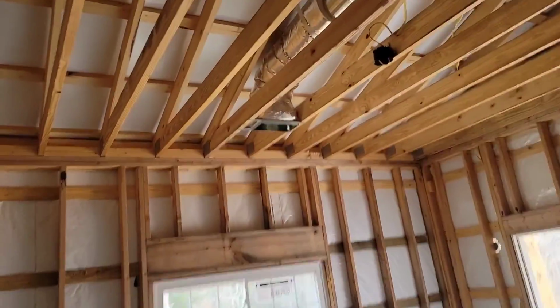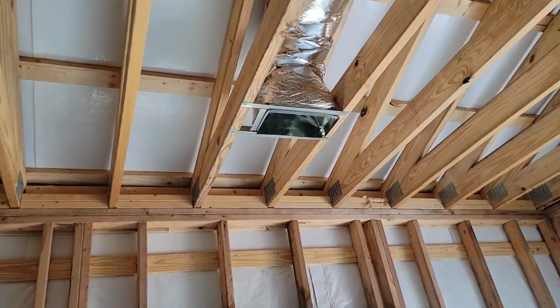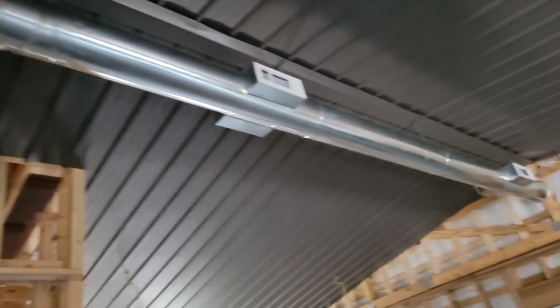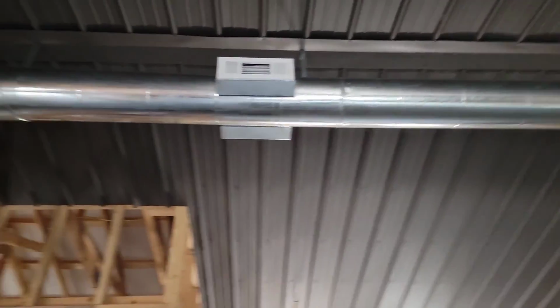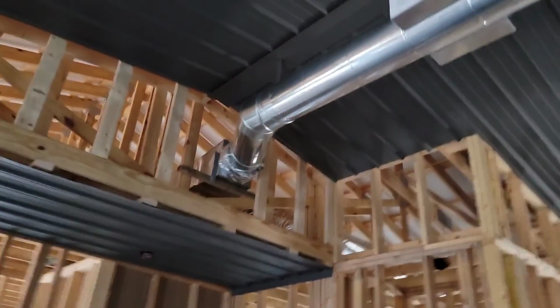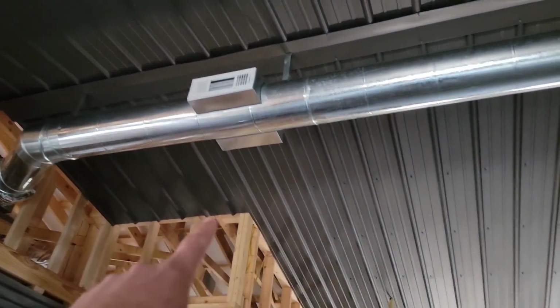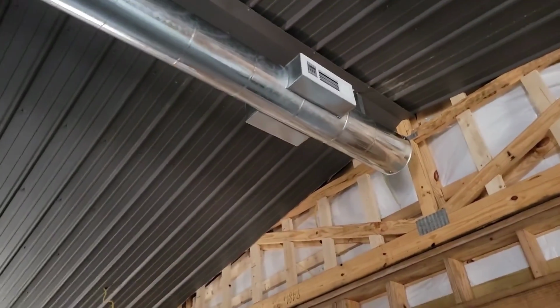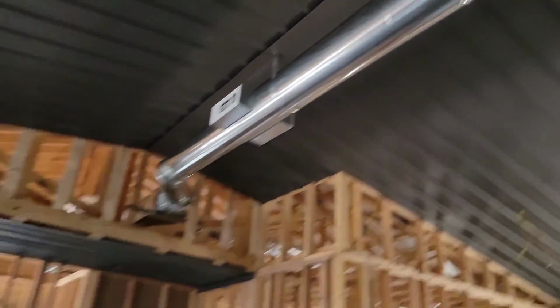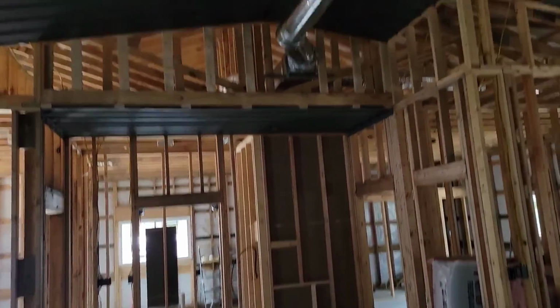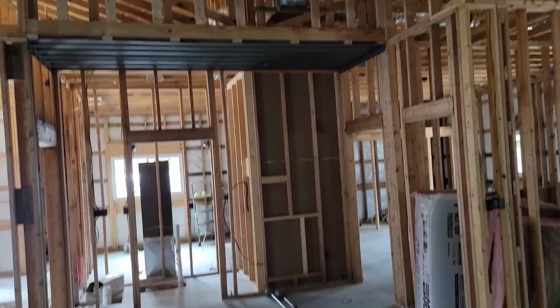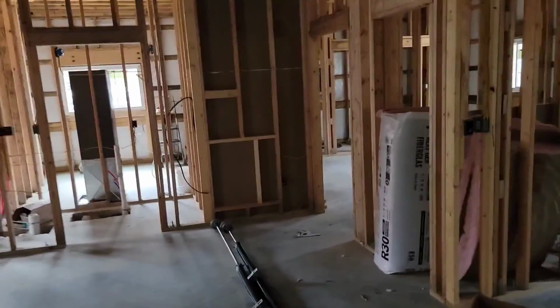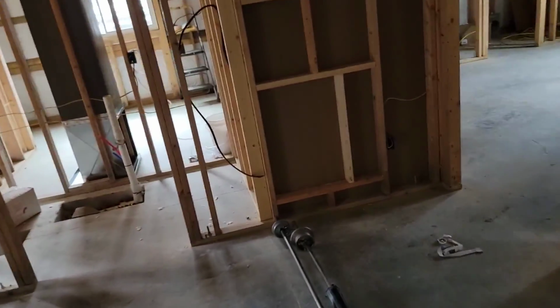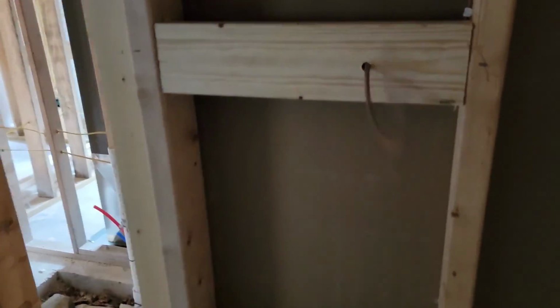This is a bigger room. That's another 8, so 700 to 800. And then this was all open. So we've got that exposed round pipe, 9, 10, 11, 12. So that's 1200 CFM as far as the vents, and it's a 3-ton unit, so that's perfect. Here's where our return is going to be, 20 by 30 return. And here's our thermostat wire.